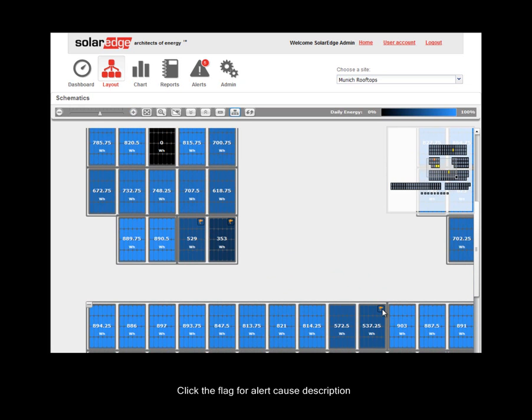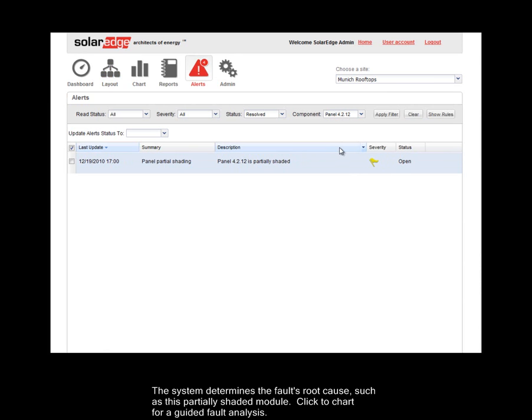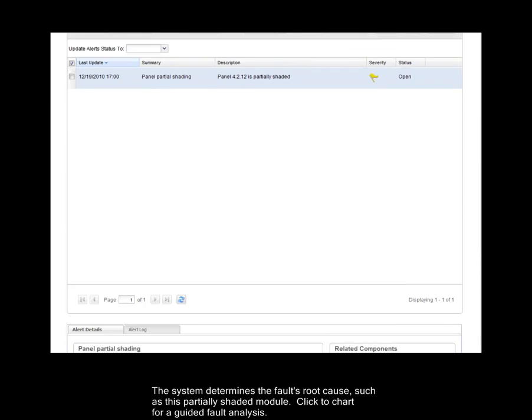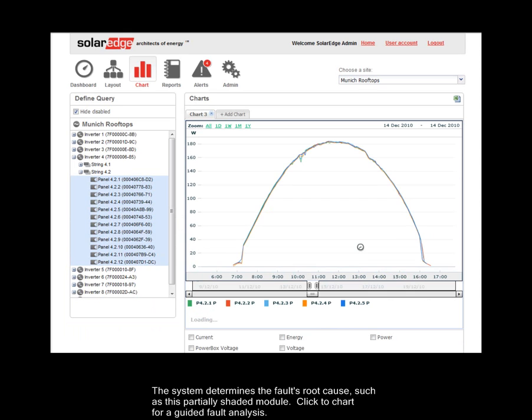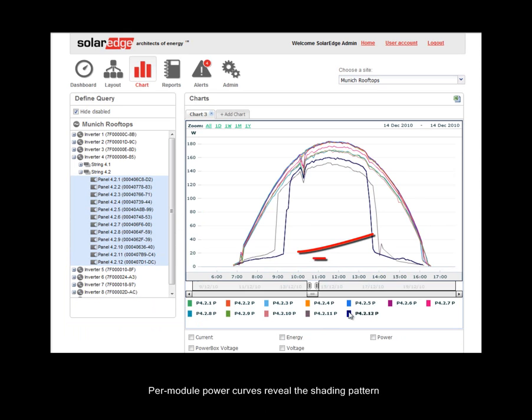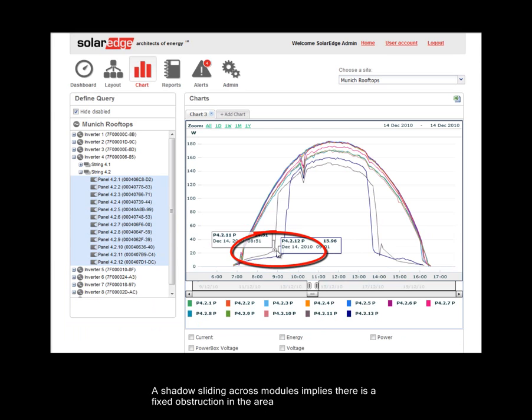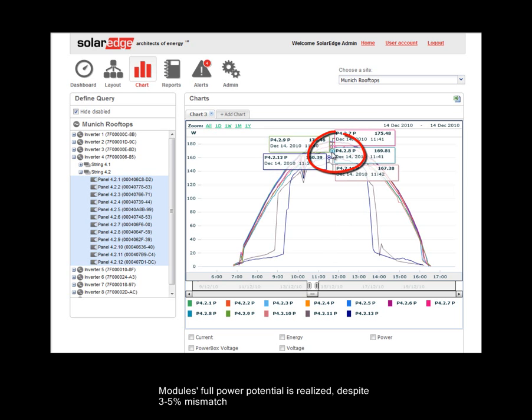Click the flag for alert cause description. The system determines the fault's root cause, such as a partially shaded module. Click the chart for a guided fault analysis. Per-module power curves reveal the shading pattern. A shadow sliding across modules implies there is a fixed obstruction in the area. Modules' full power potential is realized despite 3-5% mismatch.